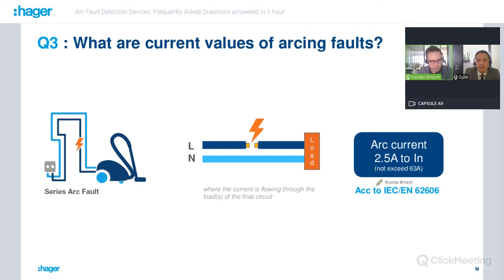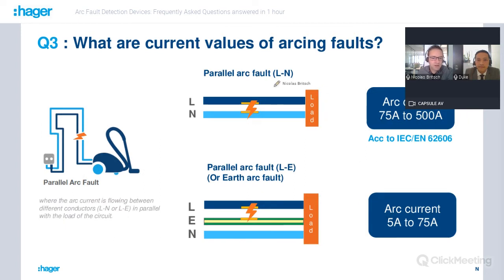And according to the product standard EN/IEC 62606, then we are talking about parallel arc faults. Here the current values are a little bit higher, of course, because the fault is between two different conductors, so there is much more current. And in the standard, the test starts from 75 amps and up to 500 amps for parallel arc fault between phase and neutral. There is another kind of fault, which is parallel arc fault between phase and earth. And here the current values are a little bit lower. It starts from 5 amps and up to 75 amps.